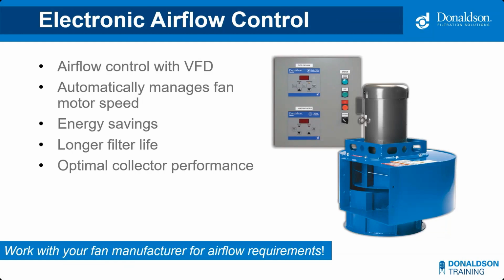These, when working together, will automatically manage the fan motor speed so that the fan is only used as much or as little as is needed for optimum performance. For example, when the filters are getting towards the end of their useful life, the VFD will speed up the fan to overcome the additional static pressure so the system is still performing at its designed airflow.